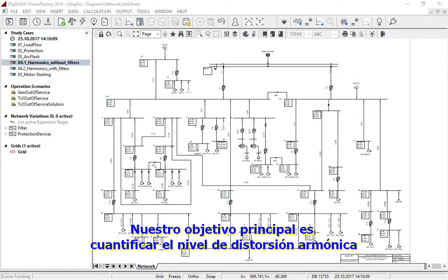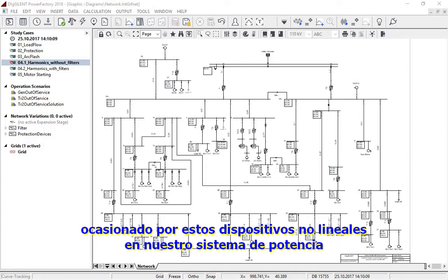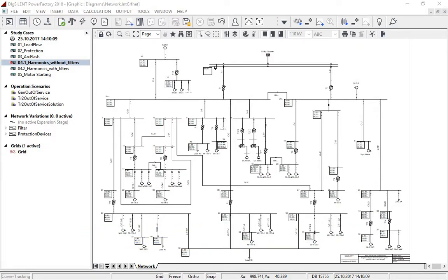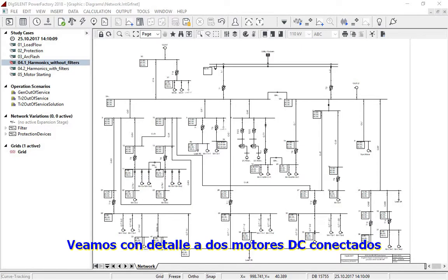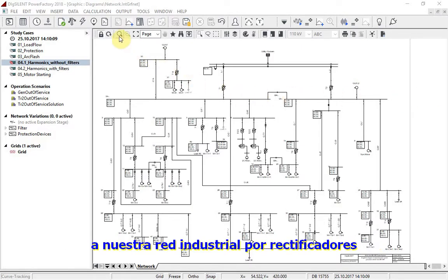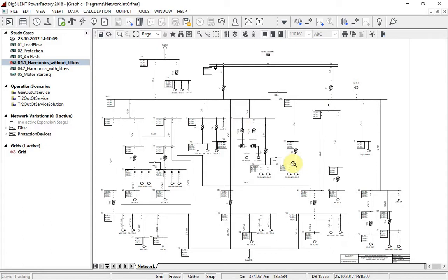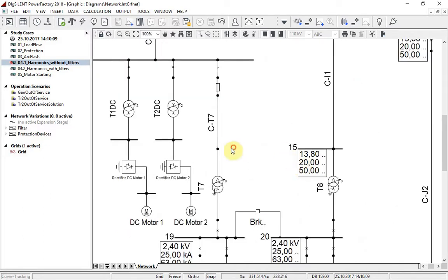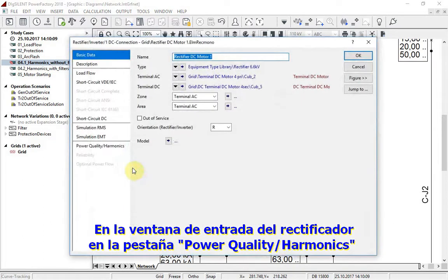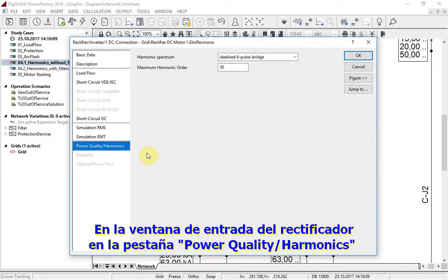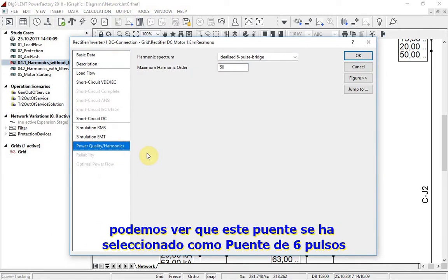Our main goal here is to quantify the level of harmonic distortion caused by these non-linear devices in the power system. Let us have a look at two DC motors that are connected to our industrial network over rectifiers. In the rectifier input window, under the tab Power Quality, Harmonics, we can see that this bridge has been selected as a 6-pulse bridge.